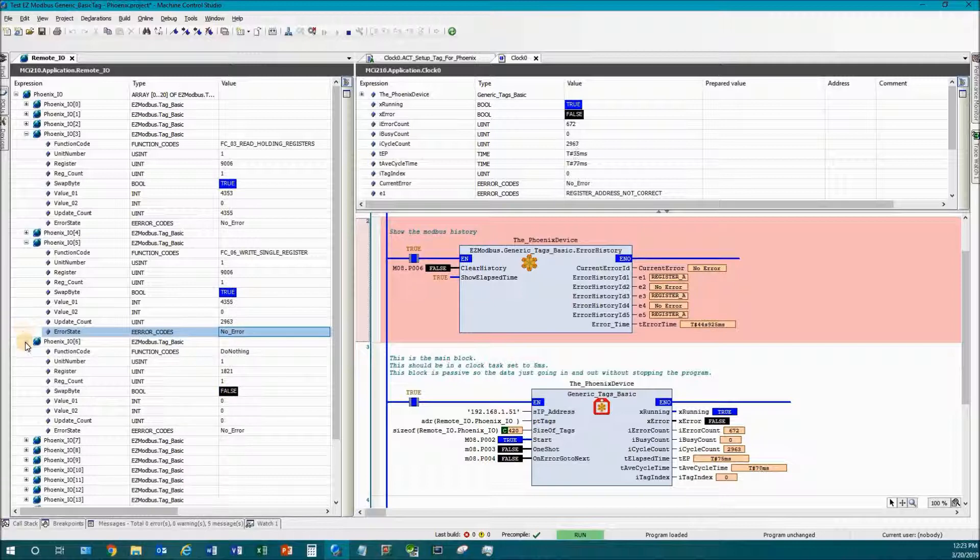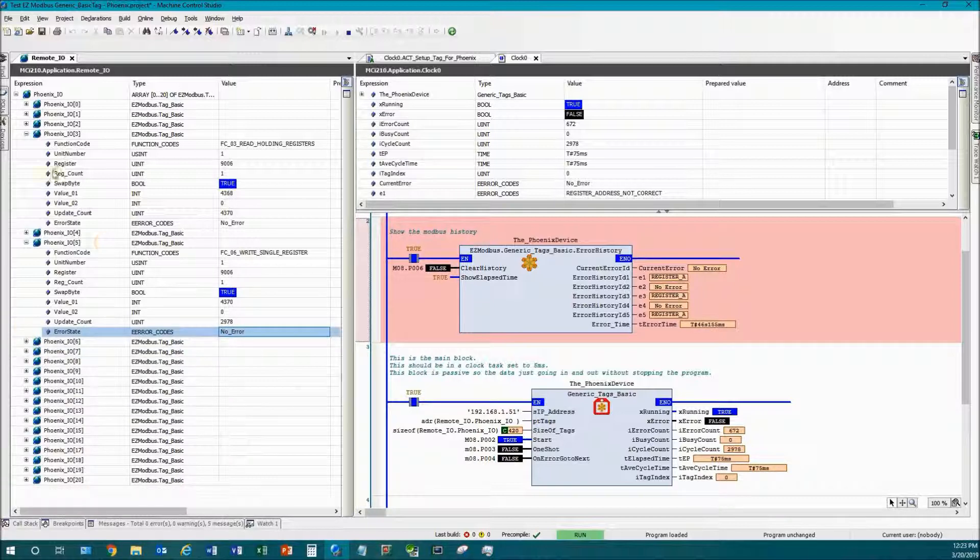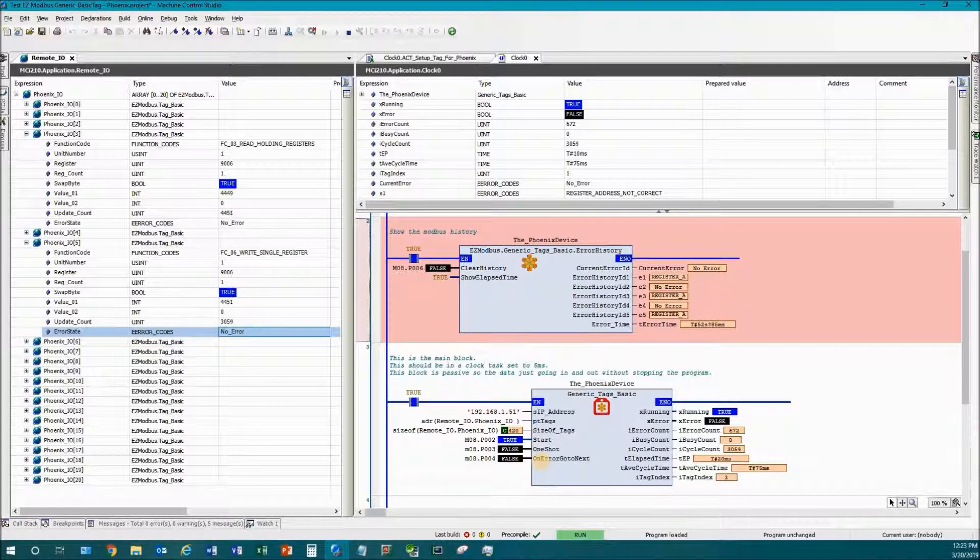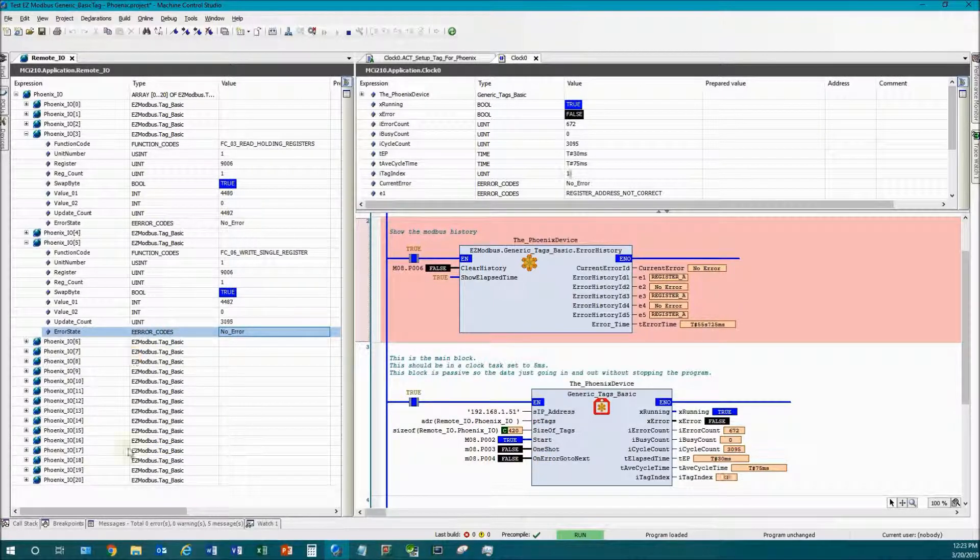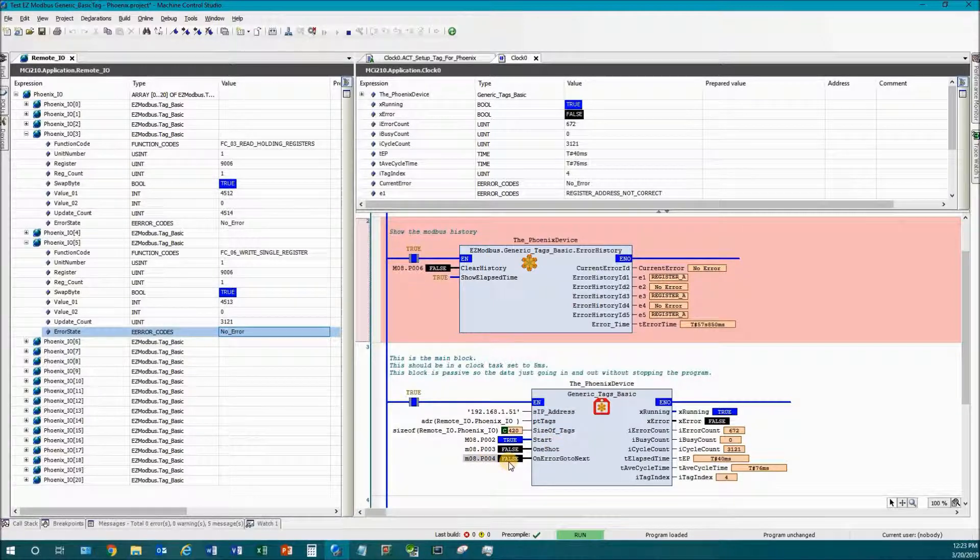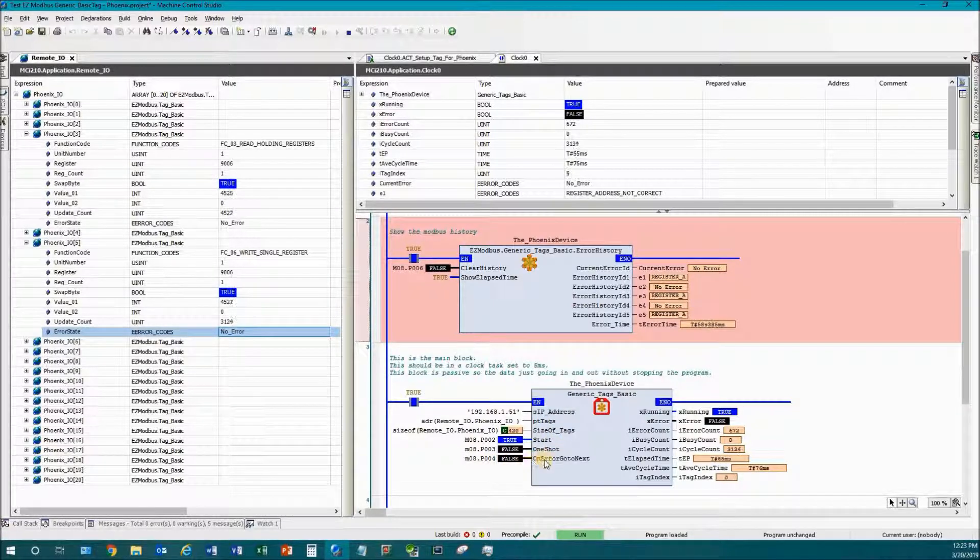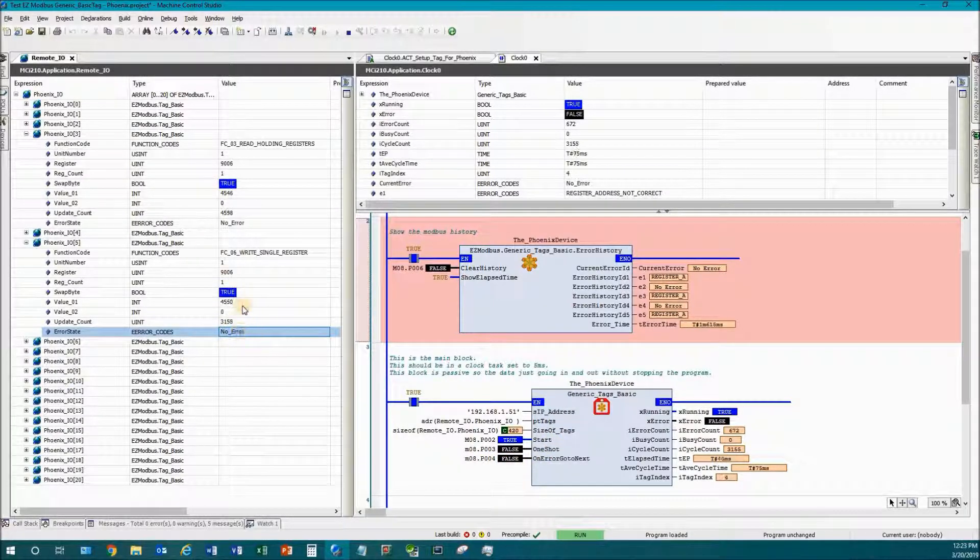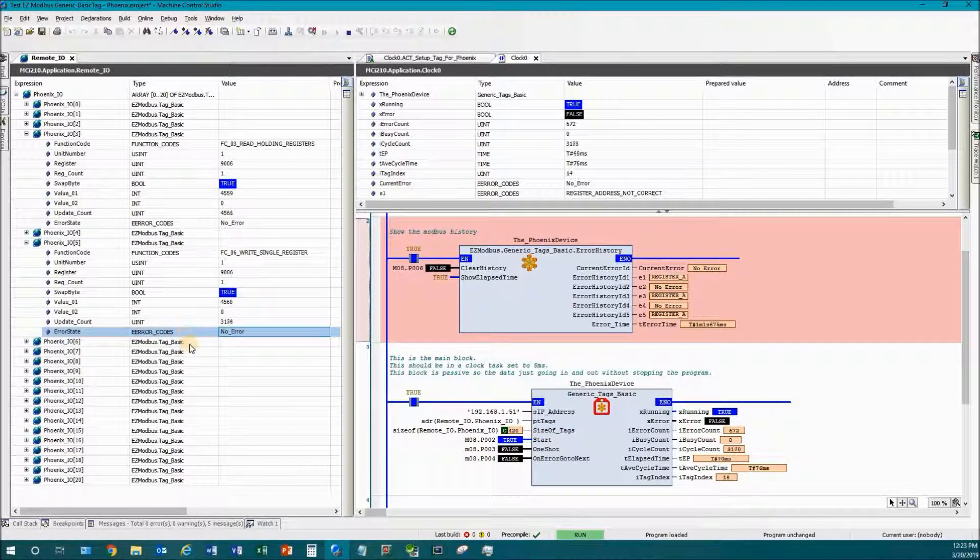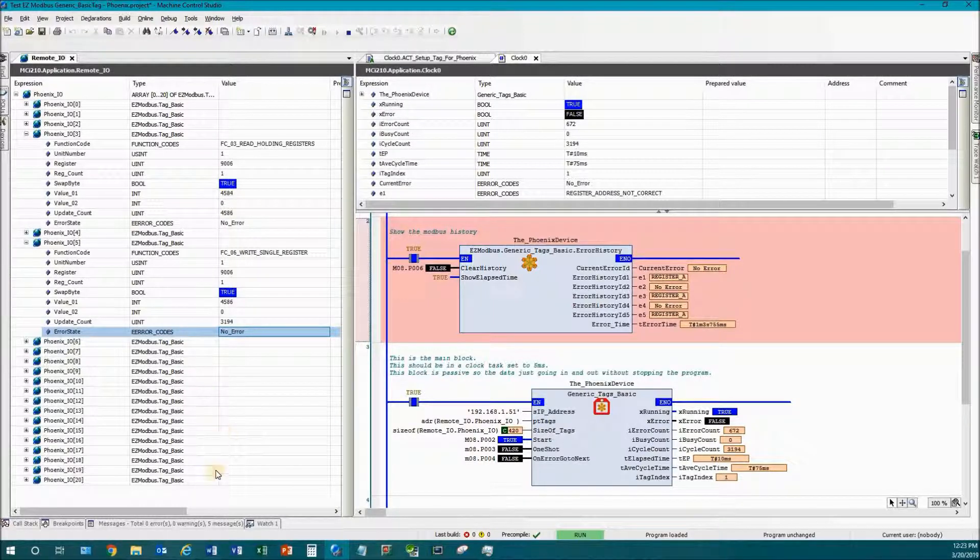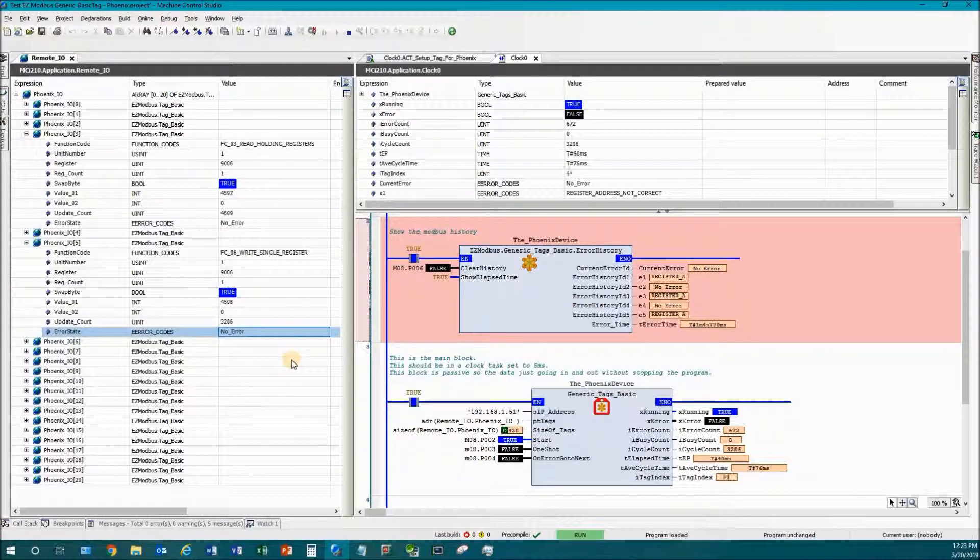What this on error go to next means is if this is off like it is here, then it'll go down the tag list and once it hits an error the next tag below it would not execute, it wouldn't even try, it would just start back at the top and work its way down. That is its default behavior. If you want it to just go on and read and write all the rest of the tags then you turn this on, and it would say I know I had an error here but I'm just going to keep trying with the rest of these and see if they work.